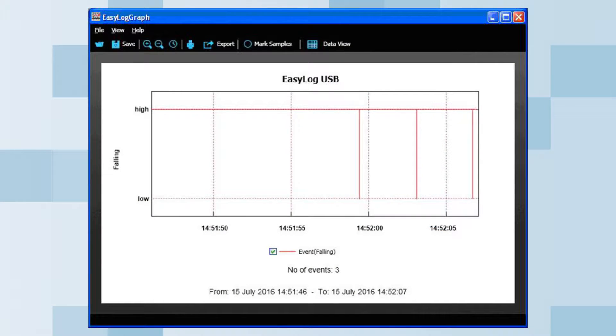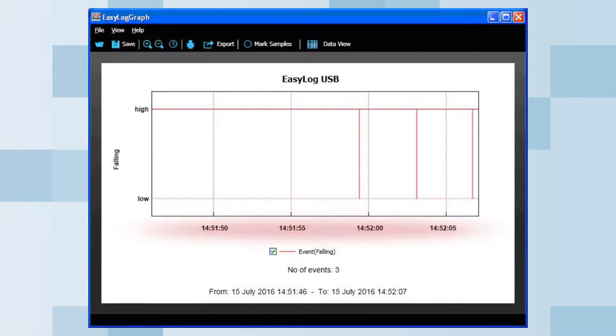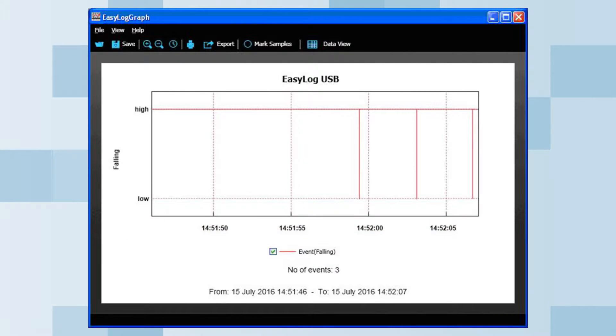In this graph, you have the event mode. In this example, there are three presses of a normally open switch. The recorded data shows you the time each switch press was recorded. On the graph, each switch press is represented by a single vertical line. In this mode, there is no corresponding line recorded when the switch is released. Note in this mode, you cannot determine how long the switch was pressed for.